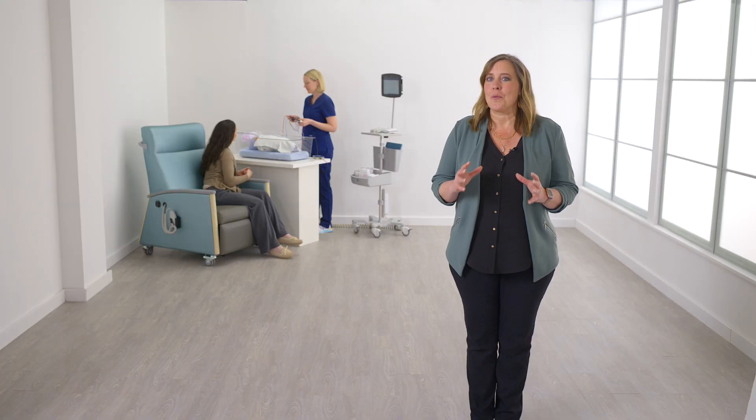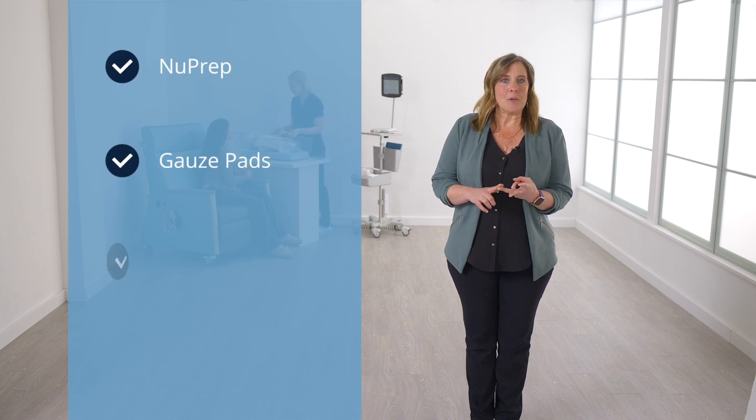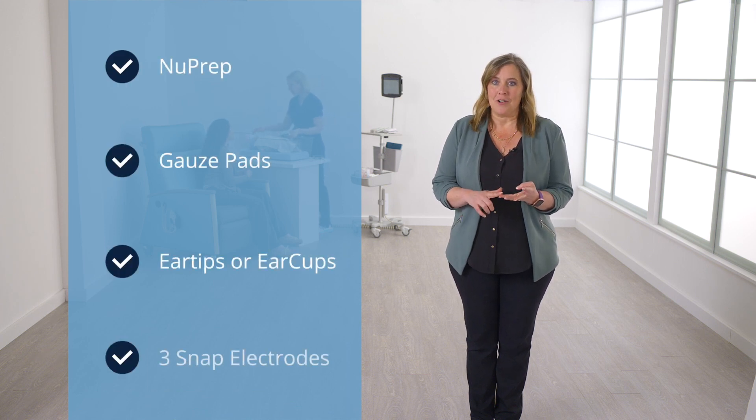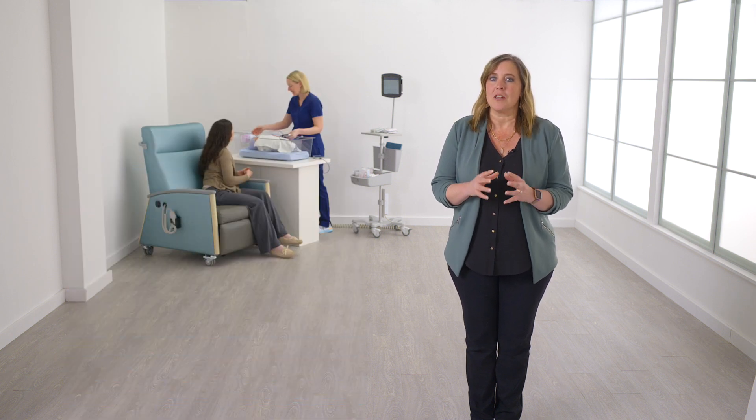The next step is patient prep. Make sure you have the following supplies: NuPrep, gauze pads, ear tips or ear cups, and three snap electrodes for ABR testing.